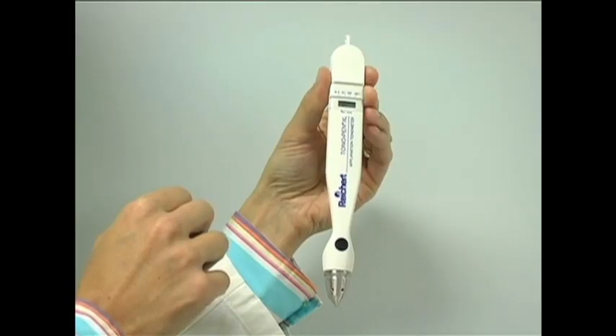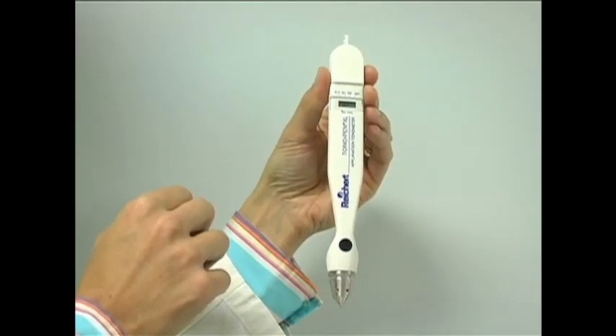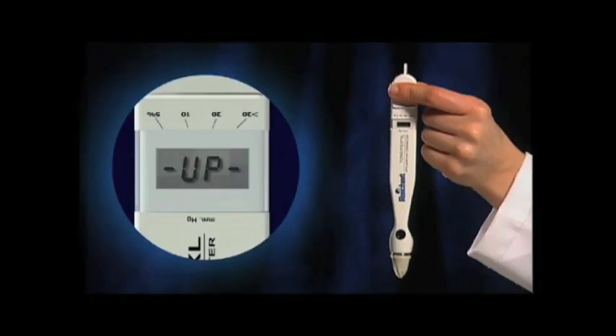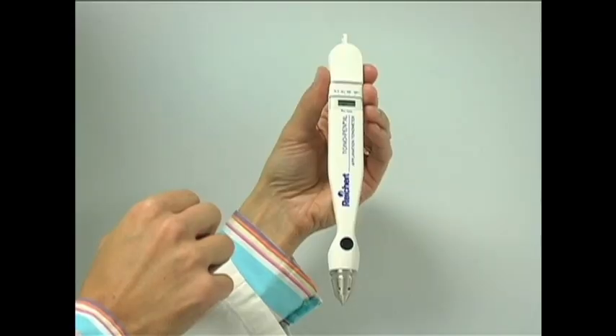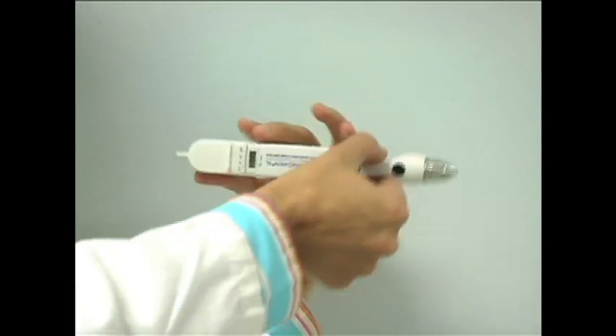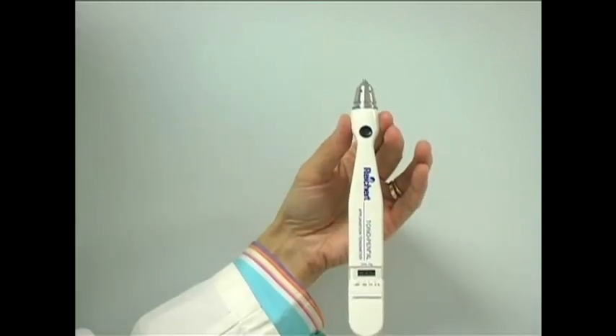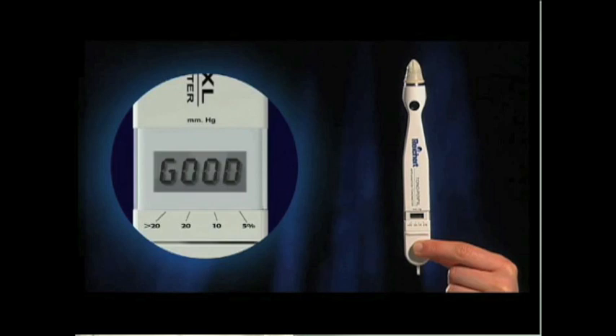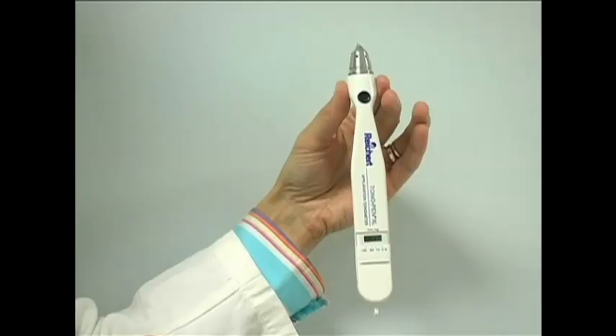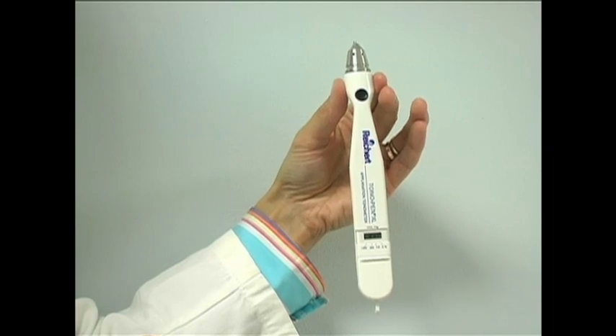Once you see CAL, keep the tonopen straight down for 15 seconds until you hear the beep and see up on the LCD display. Turn and hold the tonopen up until it beeps and you see good on the LCD screen. Now you're ready to go. If you receive other output, calibration should be repeated. Low batteries or a need for maintenance are often the reasons for difficulty in calibration.